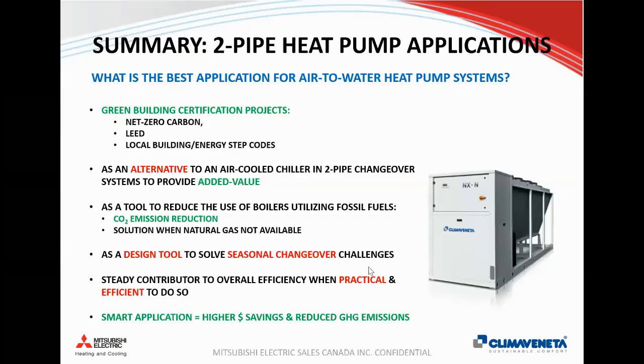So again, just to summarize, what's the best application for air to water heat pump systems? The more creative and outside the box thinking you can do, the more success you'll have with it. But certainly if you have green building certification projects like net zero carbon, LEED, or even more stringent local building energy codes, this is the product that you'll want to look at. Specifically to 2-pipe units, think of the heat pump as an alternative to a traditional chiller and 2-pipe changeover systems to now have the benefit of providing heating in the wintertime whenever that chiller would normally be shut off.